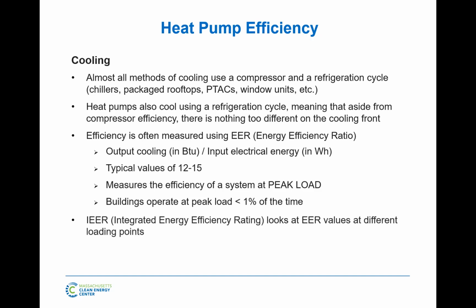So what happened is, in 2010, 9 years ago, AHRI looked at this and said, especially these VRF systems are really designed for part load. Let's take a look at the EER at different load points. That's what the IEER came from. So just to compare, the IEERs of VRF systems range from 16 to 26, an average being in the low 20s. So if somebody's asking you what the EER efficiency of VRF is, and that's all they're looking at, they're not getting the right picture, because they're going to see 12.8, 13.2, and they're going to say, can't I get a packaged rooftop unit that's pretty cheap for the same EER or close? And you can say, yeah, you can. But it's the IEER that's the big difference. What that means is VRF systems are almost twice as efficient at 50% load than they are at full load. That's both for cooling and usually for heating.